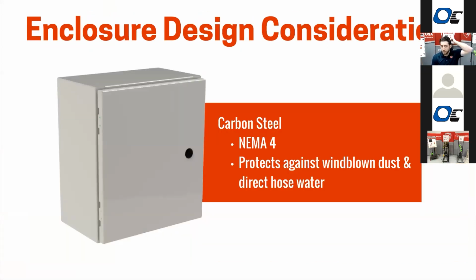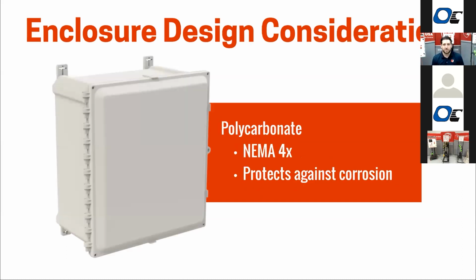Enclosures in general, a couple of design points here. At a minimum, I think you'd want to be designing around a NEMA 4 type enclosure, like a carbon steel with a coating on it. That NEMA 4 rating is going to give you protection against windblown dust and being sprayed down with water. One of the things I'll show you in a second is we talk a lot about the panels being protected from water, not having field penetrations into the top of these. I know a lot of these are inside, but we still have the potential for water to come down on the top of the panels. So we want to avoid that as much as possible.